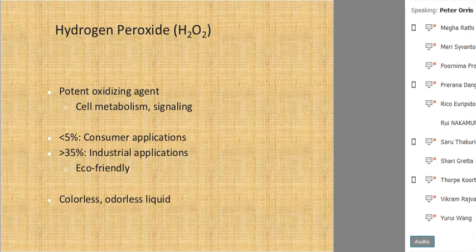They demonstrate that they can bring down a 6-log decrease in the microorganisms present, and the EPA approves that process then as an adequate sterilization process. But unless there is pressure brought to bear on these manufacturers, they will not attempt to go out and develop the alternative technologies that may be necessary for some of the products that have difficulty being sterilized with hydrogen peroxide or, in fact, gamma radiation or others.